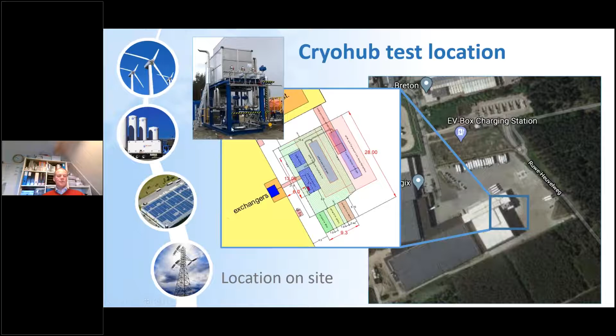The heat exchangers in the freezing cell, which generate the cold, are placed at the top of the racking. These are mobile rackings on both sides, with a stationary part in the middle, and at the top are placed the heat exchangers, as you can see a little bit in this corner. What's important is that the connection from the inside-placed heat exchangers, very close to the wall, to the outside piping going directly to the skid, is as close as possible.